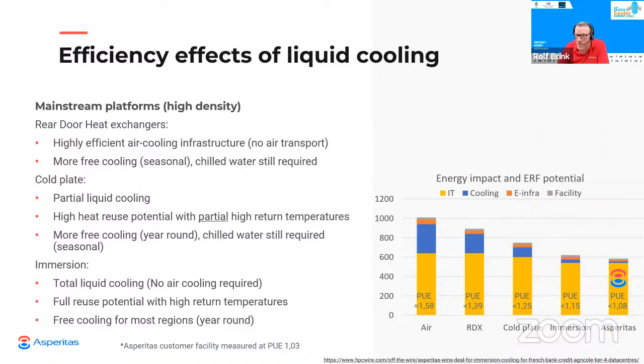However, because they function in the same way as air handlers, low temperature cooling will still be required. Cold plate implementations are allowing at least part of the infrastructure to work with elevated temperatures, which in turn allow more efficient and compressorless cooling measures. Cold plate also allows a minor reduction of IT power due to the capture of heat within the chassis, although usually limited to the main heat sources.